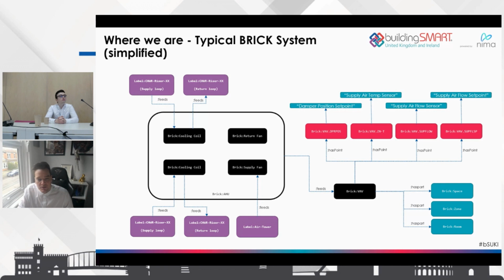Now these are the data points from that VAV - this is what that VAV is communicating, or what is being fed back to it: damper positions, which is the set point of where the damper sits; supply air temperature sensors, airflow sensors, and all the sensors within that room or in that piece of duct; and then the airflow set point, which will be the manual or automatic air set point, depending on the settings in the room.